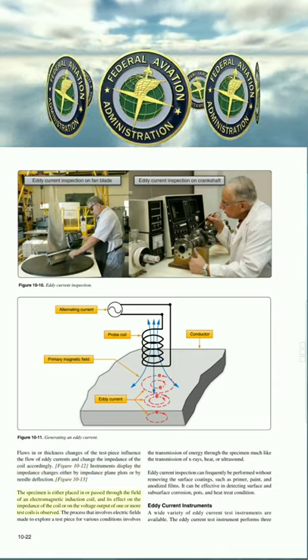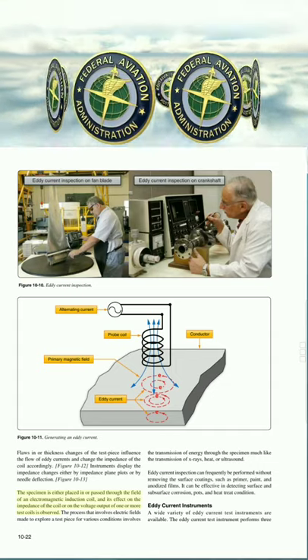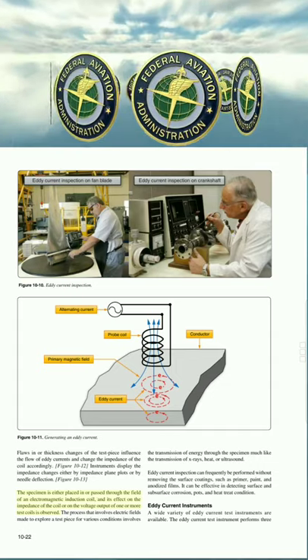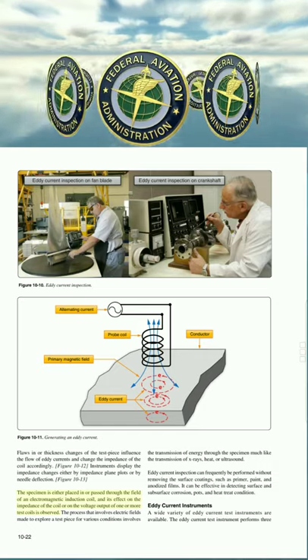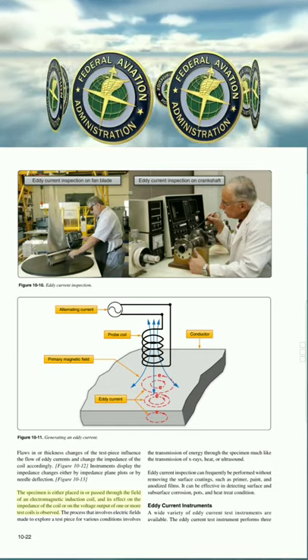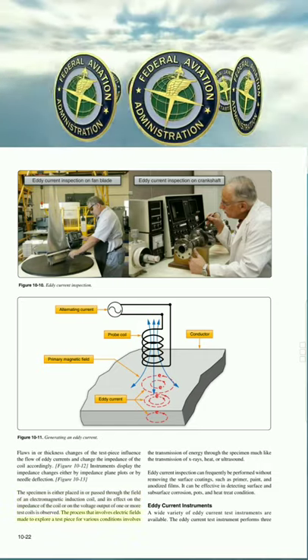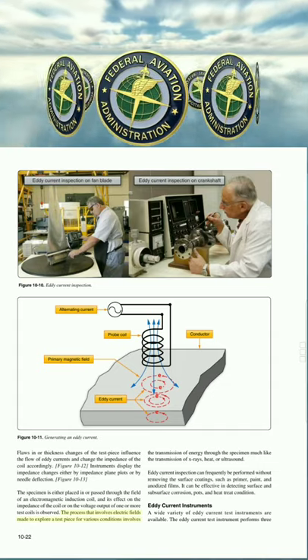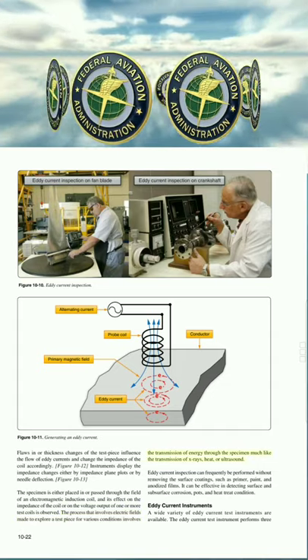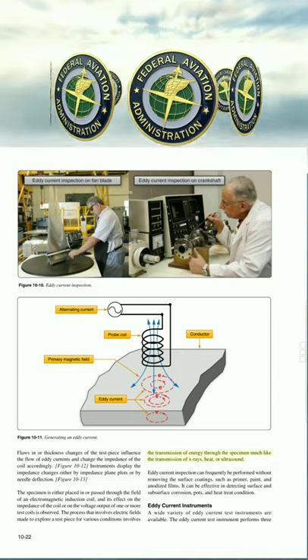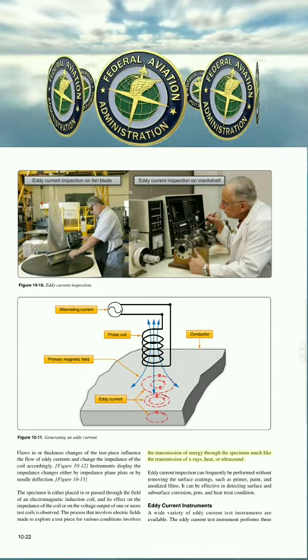The specimen is either placed in or passed through the field of an electromagnetic induction coil, and its effect on the impedance of the coil or on the voltage output of one or more test coils is observed. The process that involves electric fields made to explore a test piece for various conditions involves the transmission of energy through the specimen, much like the transmission of X-rays, heat, or ultrasound.